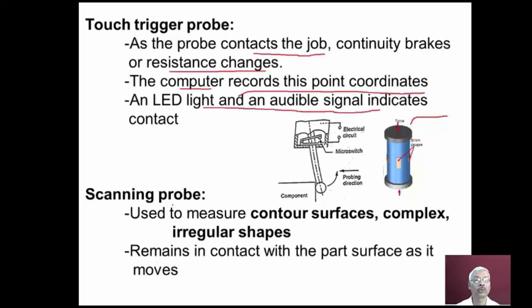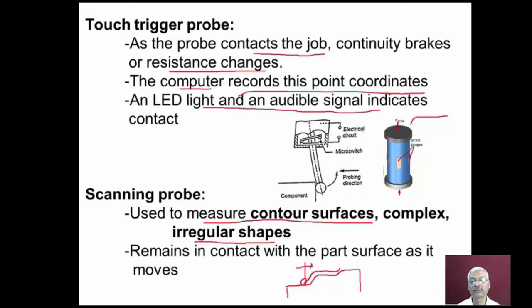In the case of a scanning probe, this is used to measure contour surfaces and very complex irregular shapes. This scanning type of probe remains in continuous contact with the part surface as it moves. When the probe moves along the surface, it scans over it and sends signals to the computer system, and hence very complex 3D shapes can be assessed using the scanning probe.